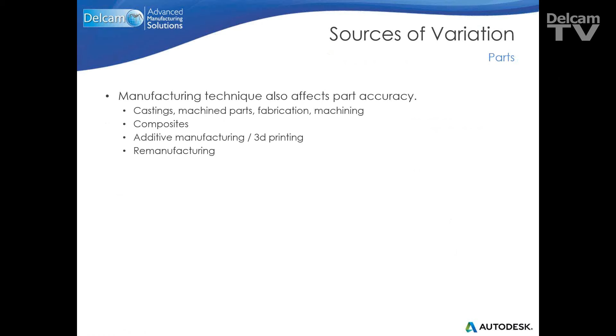Sorry, just one quick point on that. You cannot underestimate how much the component itself will have a variation on your measurement. So, for example, if you're measuring the thickness of a simple block that's 100 millimeters long, there won't be parallel faces. Those faces that you're measuring across won't be parallel. If you measure at one end of the component, you get a different number than if you measure at the other end. So that's where the part can add variance. Unless you have a procedure that says, look, we're always going to measure at the right-hand end or in the middle, or take the two readings and average, or even show the range, you will always get variation.